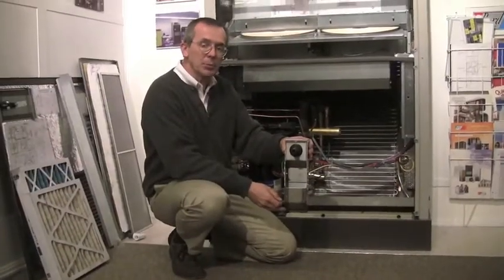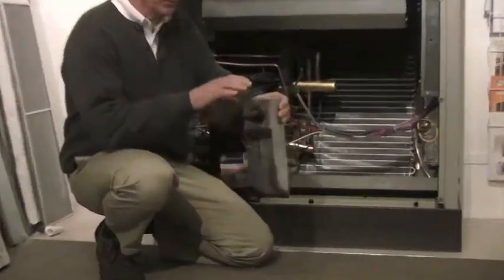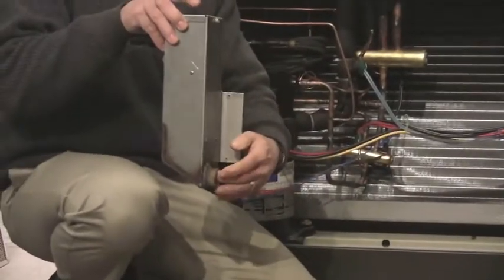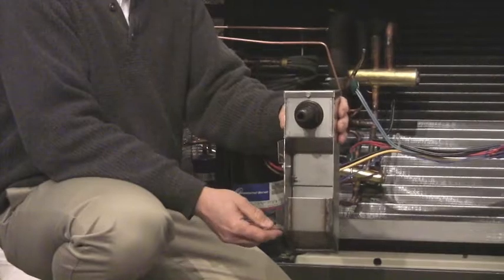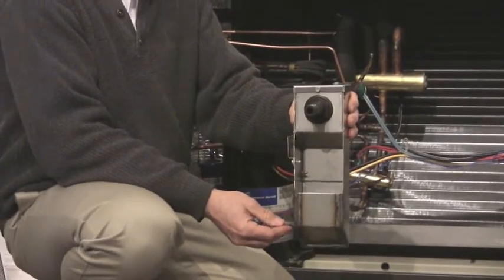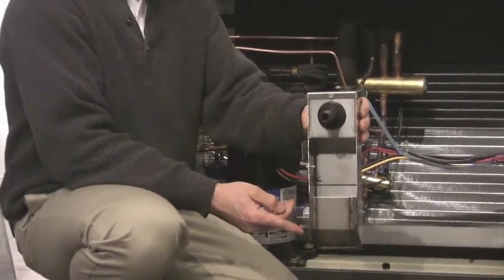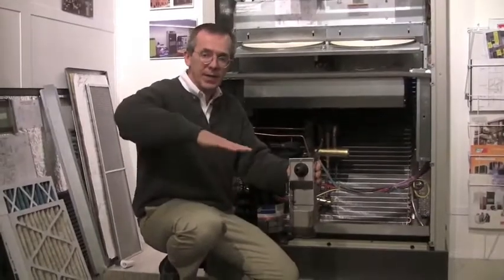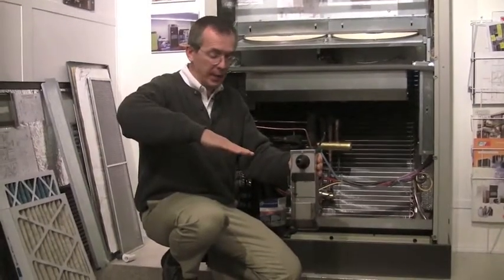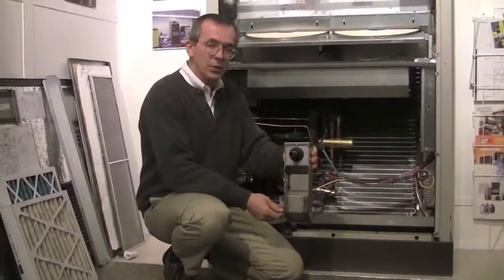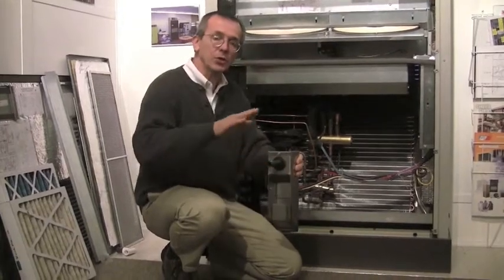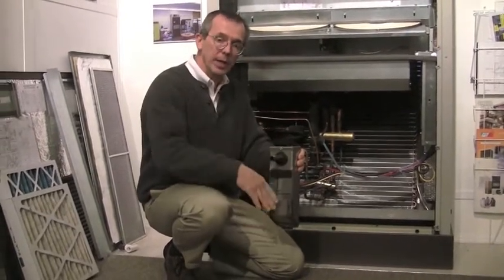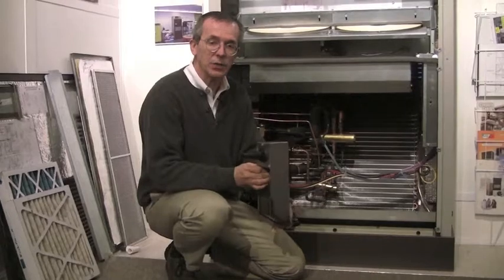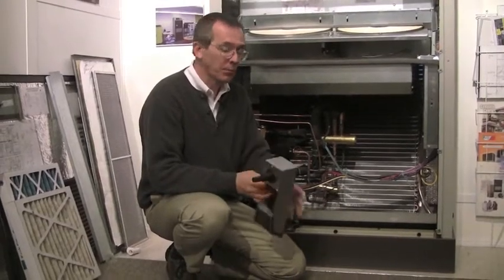This nipple is protruding into the wall sleeve, so if this stops up, water is going to go into the wall sleeve through this nipple. The wall sleeve is designed at an angle to the outside. Once this goes into the wall sleeve, it's going to drain to the outside of the building and run down the side of the building, indicating that you have a stopped up drain.